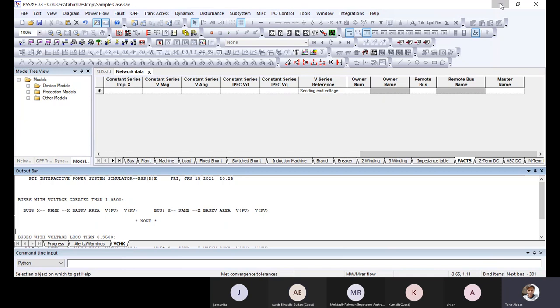Basically, we will see the per unit method in the next lecture: how to calculate the per unit impedances, and per unit from one base value to a different value, like in the transformer reactance, because every transformer has its own base. So what we do is calculate the new value of our transformer reactance based on the formula X new is equal to X old times S new over S old, basically the MVA new over MVA old. And if the voltage at one side of the transformer is the same, we can make this ratio unity, so that is the voltage squared. In this way we will see this calculation in the Excel sheet. So this is the formula.